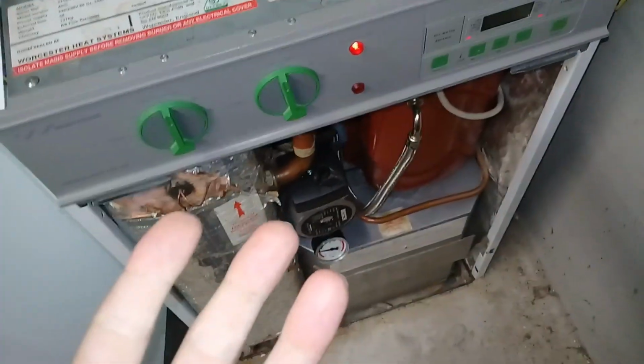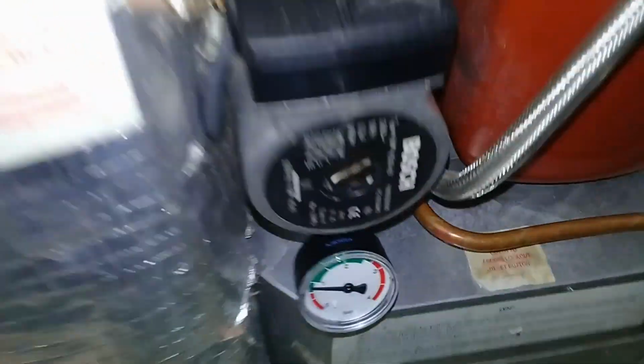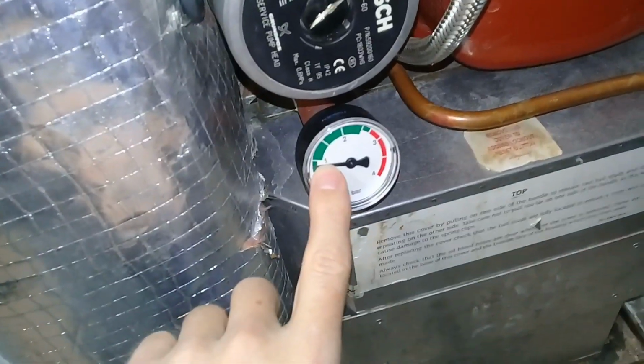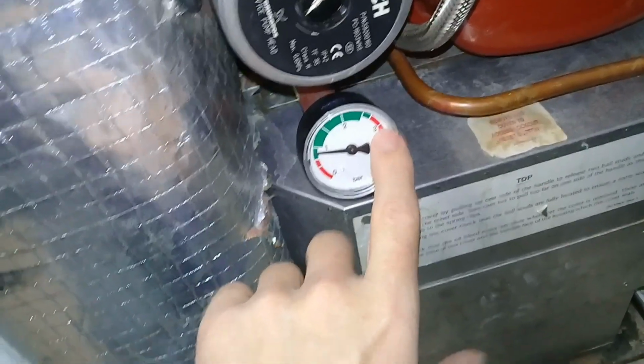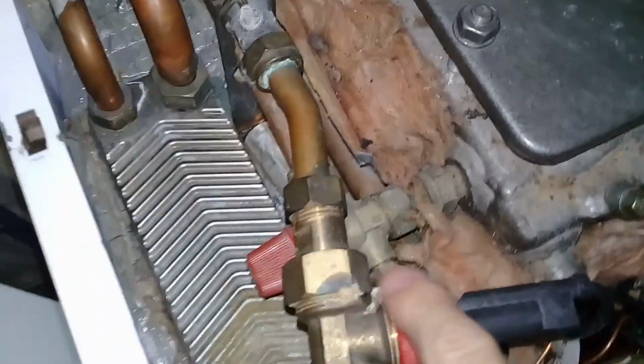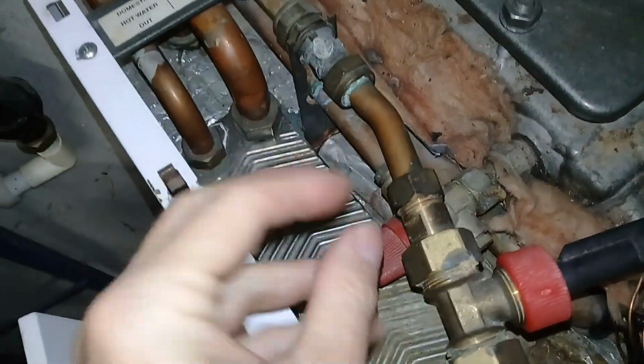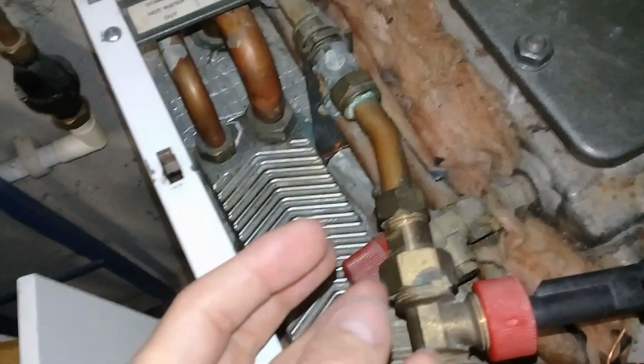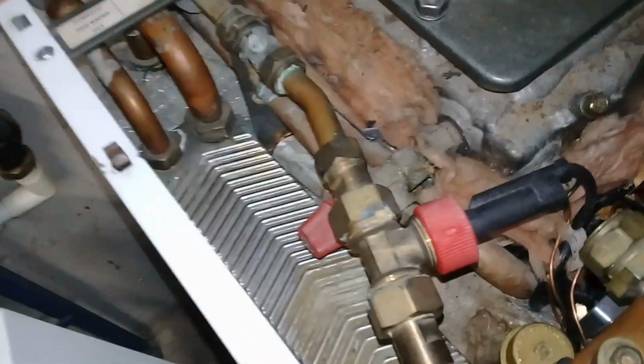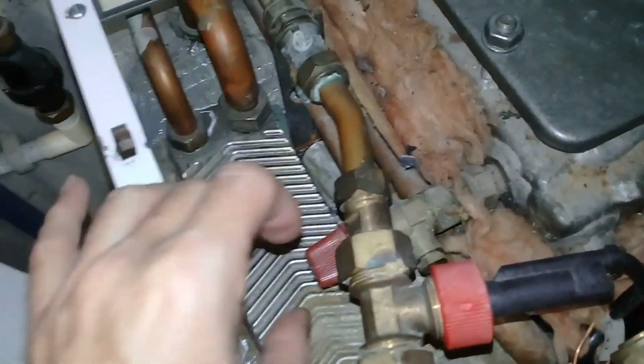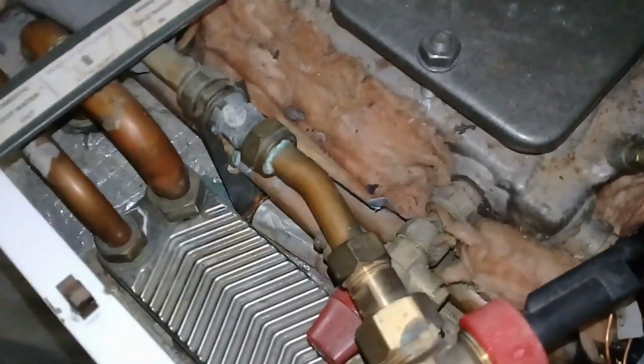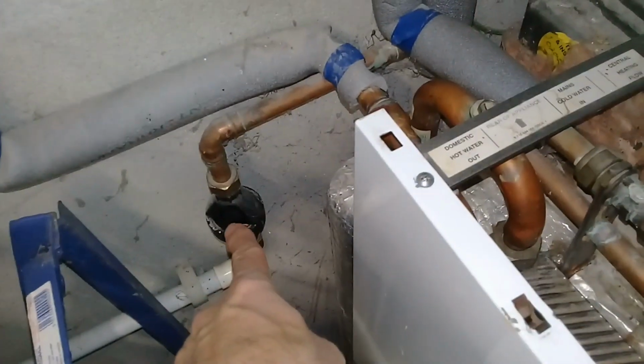When the water gets hot, everything's expanding, and what typically happens is your system pressure will rocket up towards 3 bar. At 3 bar, these boilers are fitted with a pressure release valve, which, as you can see, comes out here. If you trace the pipework back, it's this here. I won't do this, but if you twist it, it activates, and you can release some of that pressure. But apparently, if you do that, they've got a nasty habit of not seating properly afterwards. You can snap them back, but just be aware that this may leak water continuously out of the system.